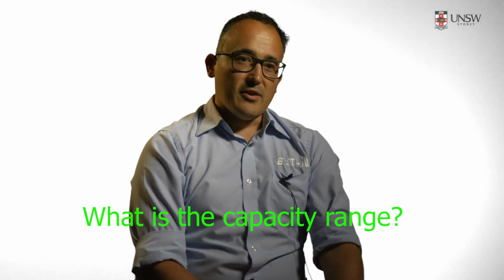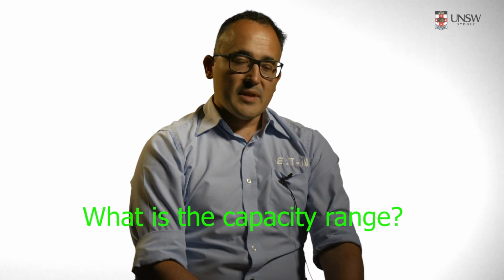management. Within our UPS systems, the batteries that we use are anywhere from a 9 amp hour block, which is quite a small battery which fits within the UPS, to a 200 amp hour battery block, which is quite large. From there we then parallel multiple strings of batteries depending on the autonomy time required for the UPS systems. So they can be in a package anywhere the size that can fit on my lap, or in a large room for a big UPS system within a data center or hospital.